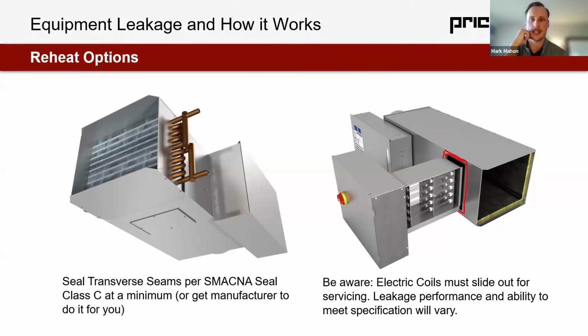And by the nature of the business, trying to lean out pricing and be as competitive as possible, that's not something we automatically do on every box, because it's not something we see for any other duct mounted heaters or manufacturers. It can be managed in that method. The other reality is electric coils simply do leak more and worse than other reheat options, which is a consideration and one I'll call out. I know I'm raising many red flags as a manufacturer, leaving engineers with questions rather than answers.